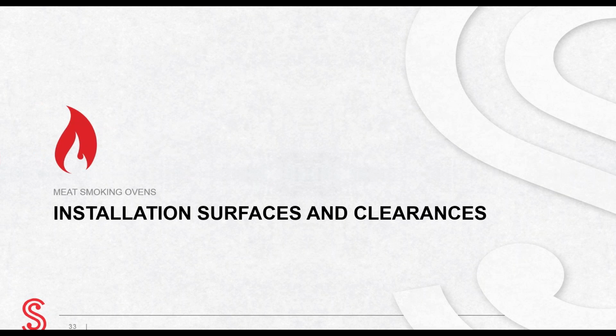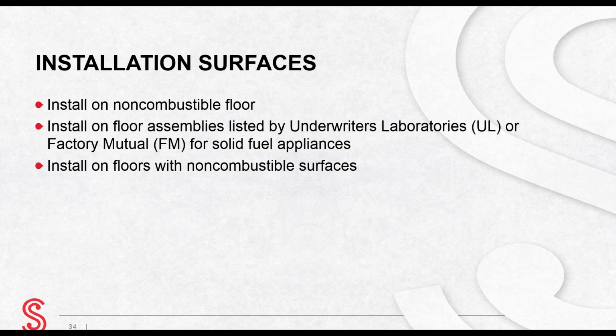We will now discuss the installation requirements for meat smokers. Meat smokers should be installed on approved surfaces. This includes the following: non-combustible floors, for example, Portland cement concrete or gypsum concrete. Floor assemblies that have been listed by Underwriters Laboratories or Factory Mutual for solid fuel appliance applications. A UL listed non-combustible floor assembly will typically include a fire-rated cement board, which has both load-bearing capacity as well as fire resistance. These assemblies will need to be installed by a qualified contractor following the UL or FM design standard. Floors with non-combustible surfaces, like a non-combustible surface over a wood floor, where they have been approved for such use by the authority having jurisdiction.